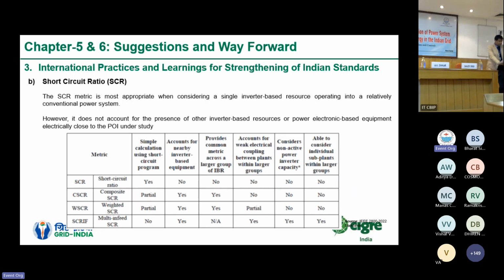So the short circuit ratio metric is a very important and most significant input to be used in tuning of the controllers. The short circuit ratio, as it is defined as of now, does not comprise the details required for carrying out the integration study of inverters. Different metrics are there in different power systems. Those can be adopted, or a mixture of them could be adopted, like the short circuit ratio, which is right now being used in our power system.